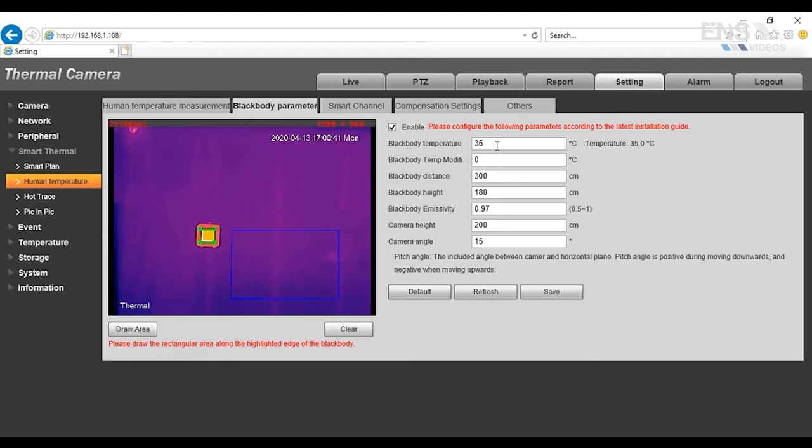You want to check the enable box, and the black body temperature is going to be set to 35 degrees Celsius by default. Now, when you first set up the black body, it's very simple. There's a power cable, and there's a switch. Now, you turn it on, you let it run for about 20 to 30 minutes, and it'll stabilize to 35 degrees Celsius, which is where that 35 degrees comes from.